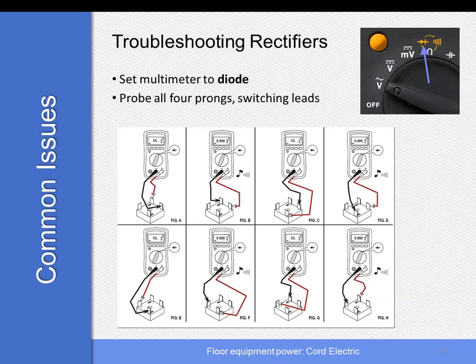To troubleshoot a rectifier, set your multimeter to the diode setting. That's going to be your standard diode symbol, which is a triangle with a vertical line. Now what is critical here is which way you put your probes, because a diode flows one direction but not the other. So if you see in the diagram how we're checking the four individual prongs on the rectifier, we actually hit each one twice, based upon which direction that diode is biased.